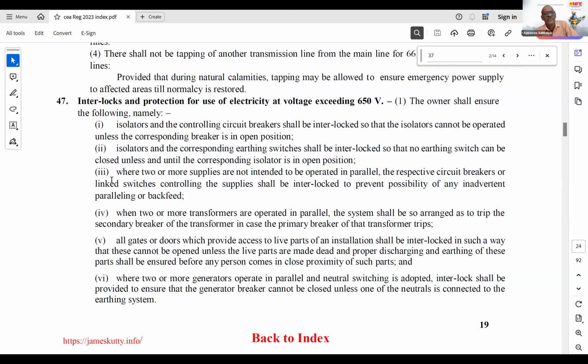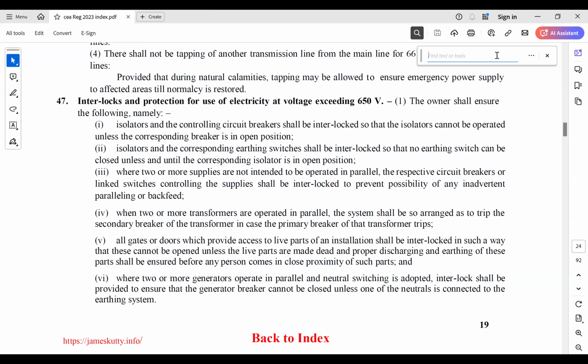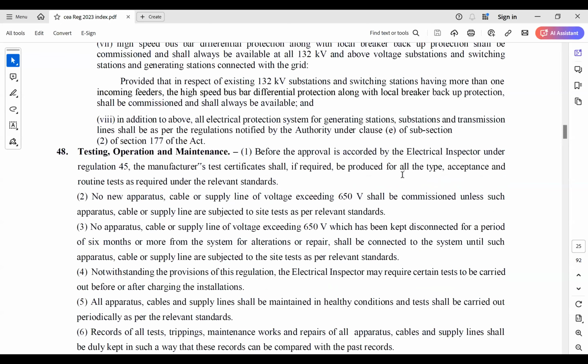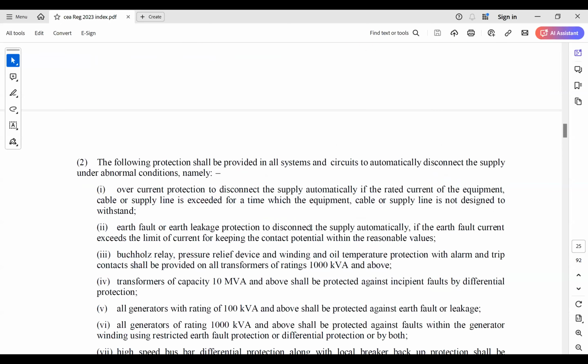Which point do you want to cover? I can tell the regulation. It shows the Buchholz relay, pressure relief device, and winding and oil temperature. That is above; you can start with that because it is a general technical point beyond 1000 kVA. But over here they have clearly mentioned that all these protections, when we talk about safety, are to be provided for transformers which are 1000 kVA and above only. So you can go through this regulation.